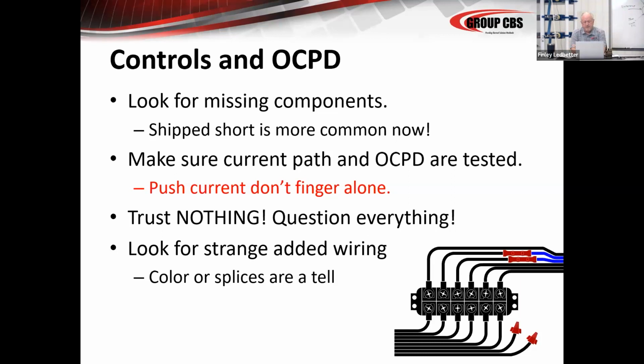Make sure you're there. Make sure all the current path and the overcurrent protective devices are tested. A lot of people just come up and finger the relays, push the trip button. If that trips the trip circuit, they believe in it. Actually push current through the circuits. Make sure everything lines up, everything runs, all the metering runs. Push current, 3-phase current if available, or there's ways to do it with single-phase current. Push current through these circuits and make sure everything functions correctly in the test mode before we get online, and then it's too late to come back and easily make a correction.